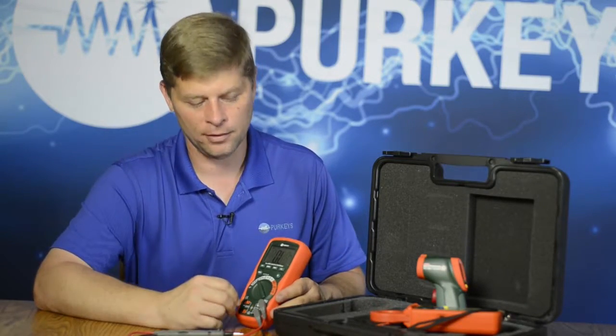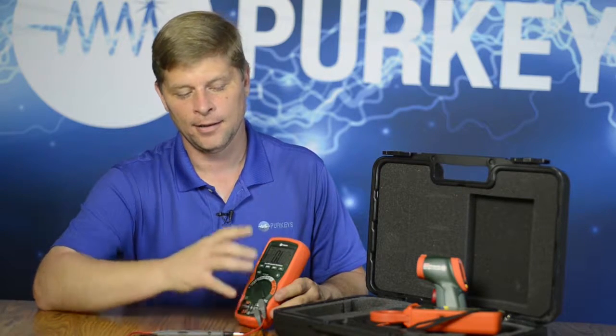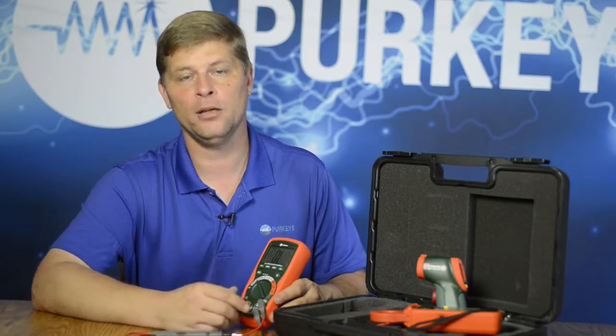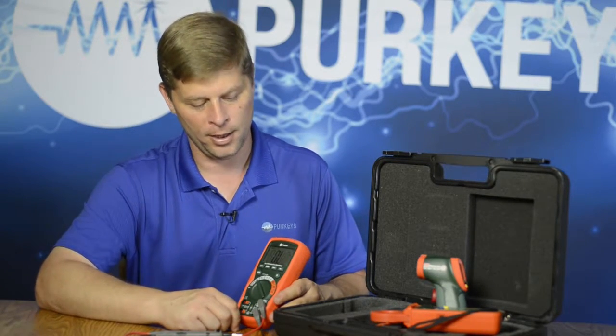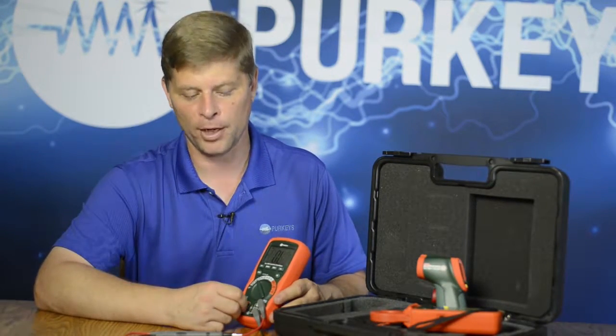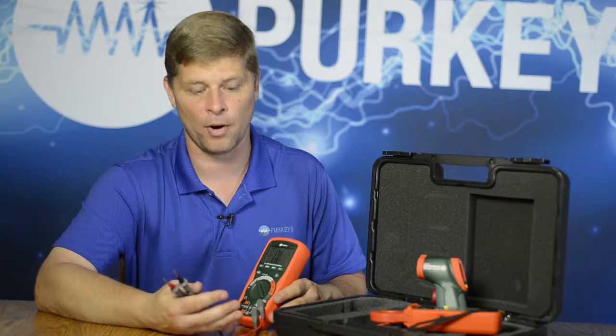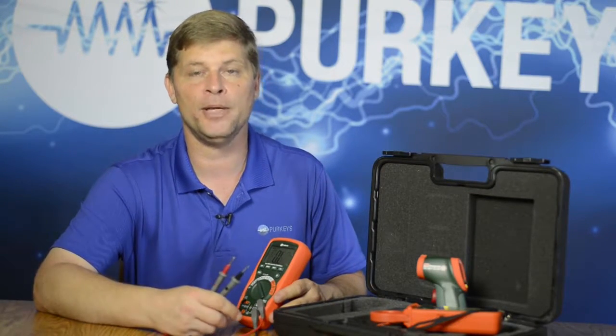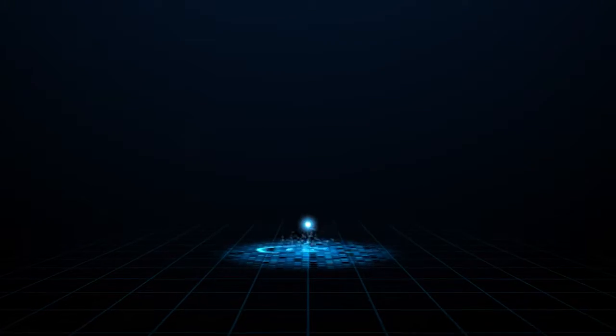A lot of times a technician will ask me, so why do I need to spend the time to do that? Well, there's an easy answer for that. All service manuals and technical bulletins are written based on, one, assuming a technician knows how to use the meter, and two, assuming the meter is in proper working order. If you have a meter that's out of calibration, you have bad or defective leads, if your meter is not right and you don't spend the time to make sure it's right, you can spend a lot of time and misdiagnose stuff simply because your meter's not right.